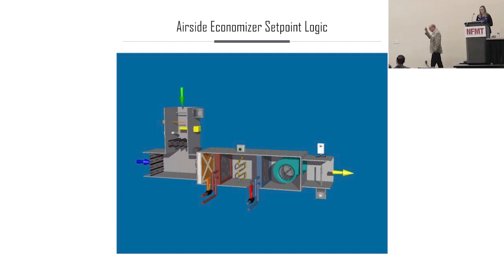So one of the other challenges, again, Alabama, lots of humidity, but we do have a winter, and so we do strive to be able to do airside economizing. A lot of times, particularly package units and others will use an enthalpy-based, that is wet bulb-based logic for the decision for the system to go into economizer mode. In a perfect world, that is the optimal way to do it, would be to follow the wet bulb. What's the liability? The liability is humidity sensors tend to fail more often than, say, dry bulb sensors. And when they fail, they tend to fail low.